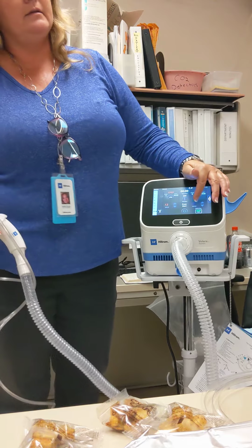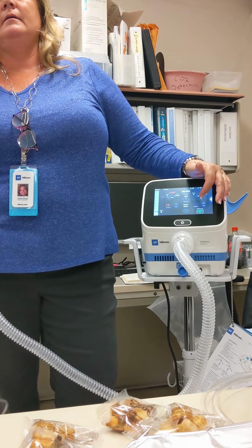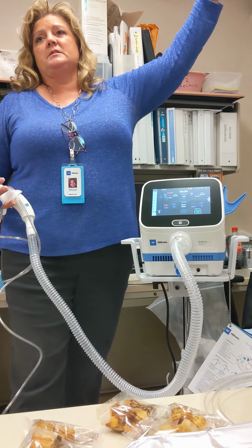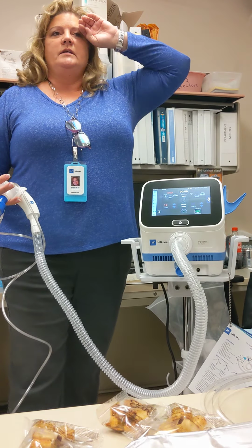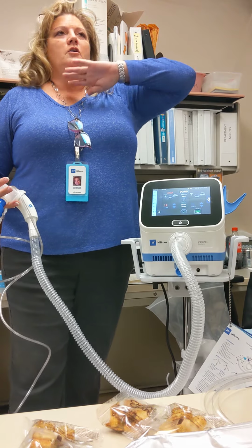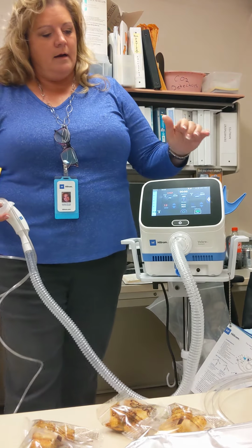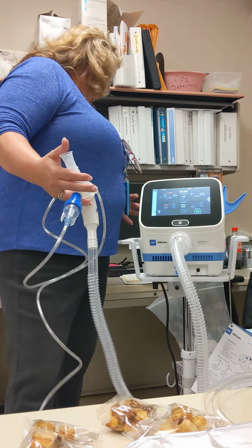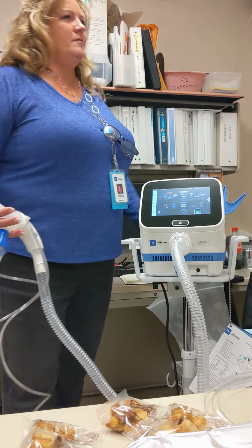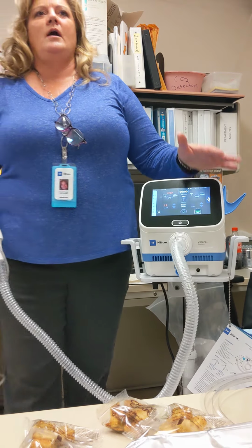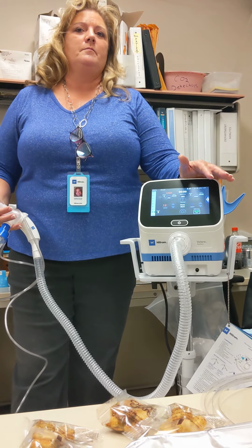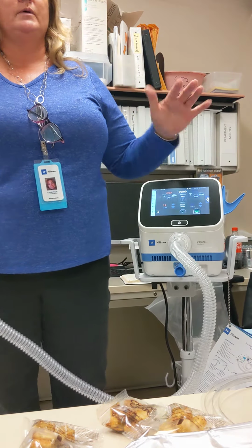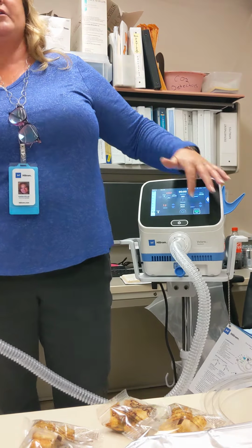Your oscillation defaults to 50. That's where we lock you out, at 50. It actually goes up to 70, but there's no reason why. We did that to mimic IPV, but you're never going to go that high. You're going to start, usually, depending on your patient, at 20 or 25.